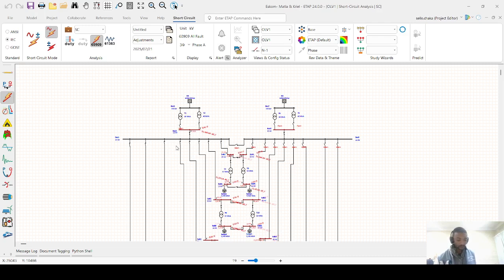Under N-1, the contingency fault level of the main 22 kV reduced because one source is out of service, but the network remains with the same operating parameters. The increase at the 11 kV substation is due to the effective sharing and redundancy. Also take note of the breaker selection: all the breakers at 22 kV must be rated above 25 kA, which is the highest fault level, and 17 kA for N-1, since at N-1 the highest fault is around 11.65, then 16 here. So that's why the selection of breakers should be 17 kA for N-1.